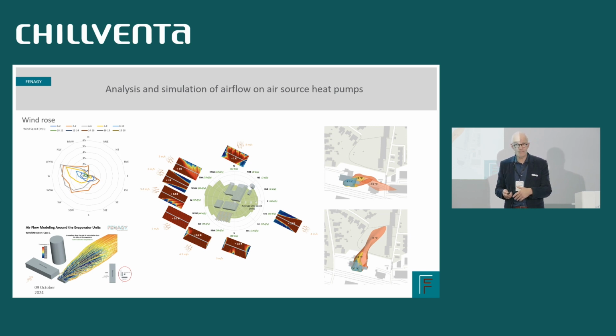So what we do internally is that we have the capacity to do CFD calculations in different wind directions and wind speeds. And of course, we have the wind roses somewhere. So for that specific location, we know the predominant wind direction and wind speed, and we can simulate what the effect would be on this installation. It's more or less necessary to do this. Otherwise, you can end up in a situation where the heat pump is not a really good piece of equipment.